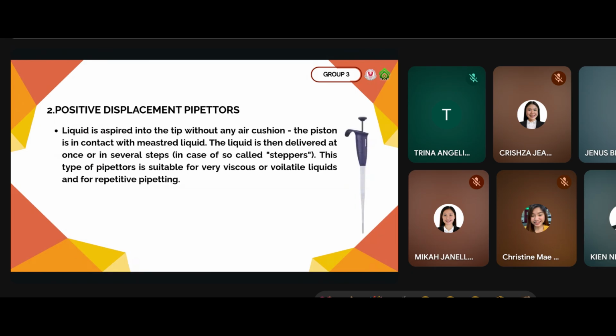The second one is the positive displacement pipette. Liquid is aspirated into the tip without any air cushion. Positive displacement pipettes work differently because there is no air cushion. The piston is in direct contact with the liquid, which makes them more accurate for viscous or volatile substances. They can deliver liquid all at once or in steps. They are very useful for repetitive pipetting.